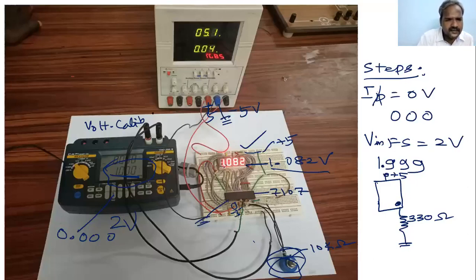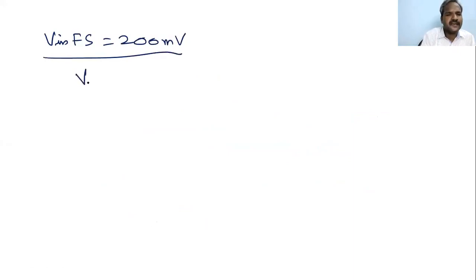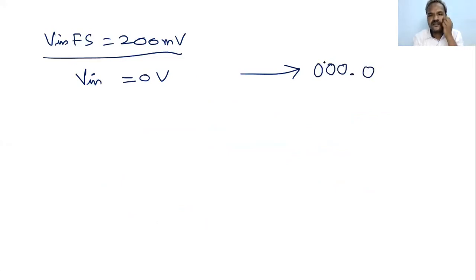So this is the input section. If the design of this 7-segment display is for 200 millivolt, what are the counts? Total counts 1999 only. In that case, we have to make the decimal in the second 7-segment, 199.9. So the calibration for Vin full scale 200 millivolt: first apply Vin equal to 0 volt. See the display, it will be 0.0. Then apply Vin equal to the full scale value, 200 millivolt.